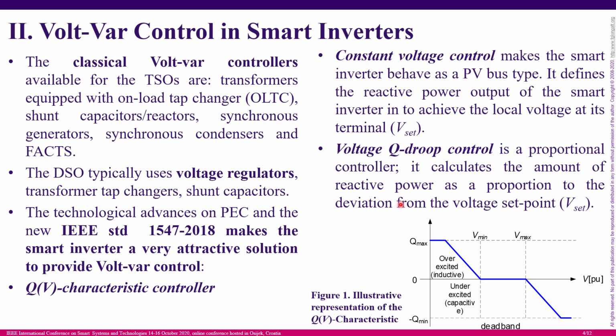All of you must be aware that Volt-Var control has been in the power system for many years, and there are several devices providing this kind of service, like on-load tap changers, shunt capacitors, reactors, synchronous generators and so on. The DSO typically uses voltage regulators, transformer tap changers, and shunt capacitors for this Volt-Var activity. However, the IEEE 1547 from 2018 makes the smart inverter a very attractive solution for providing Volt-Var services. There are several controller schemes that can be used.